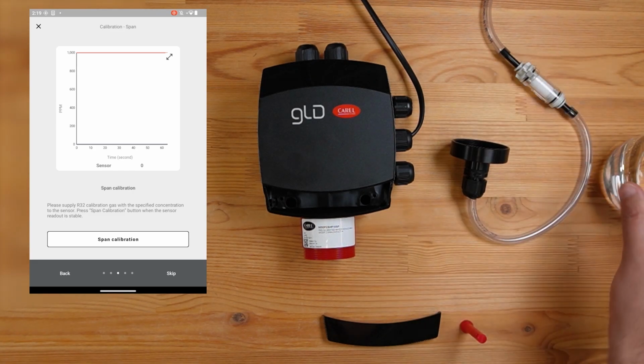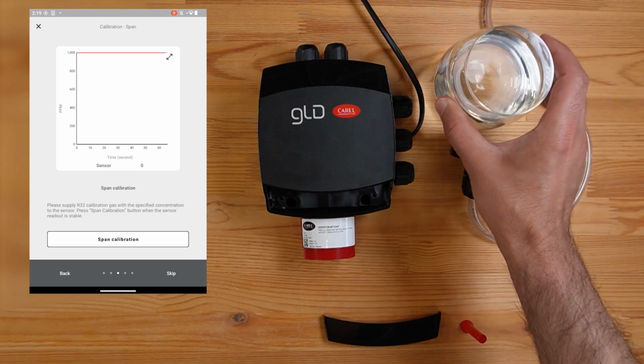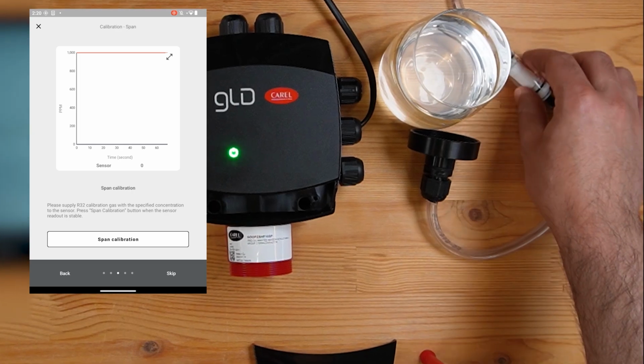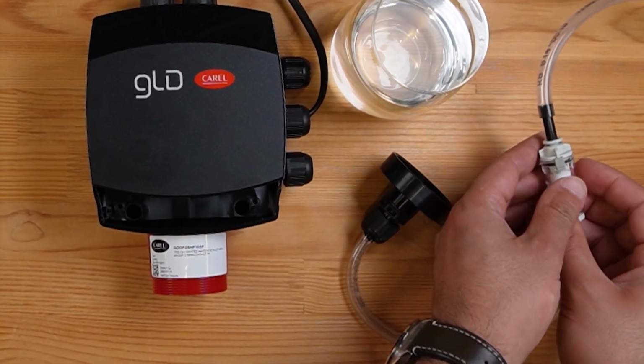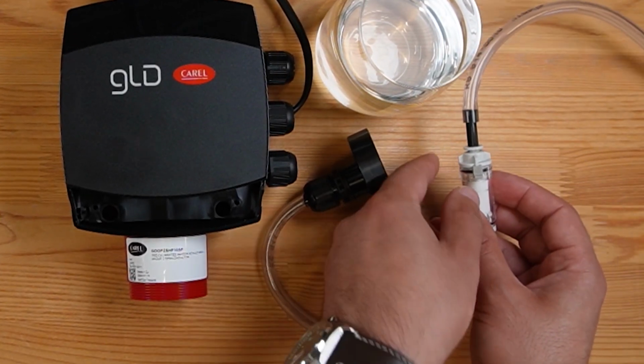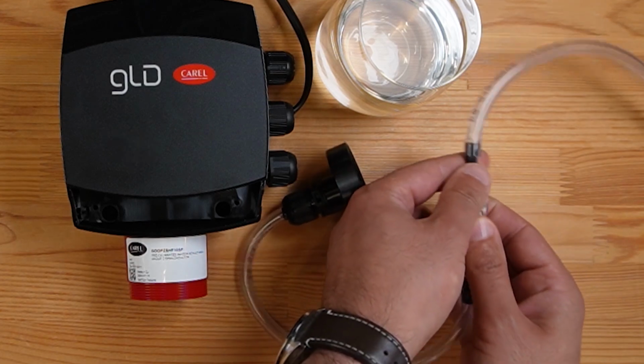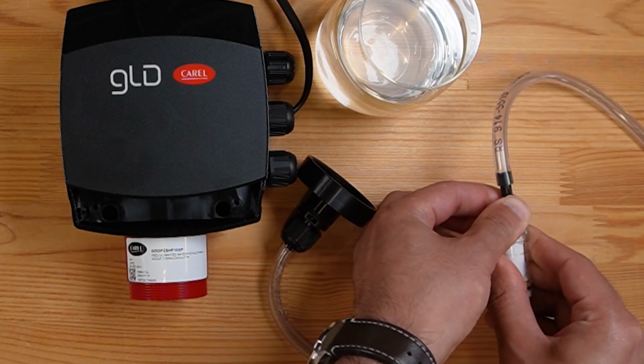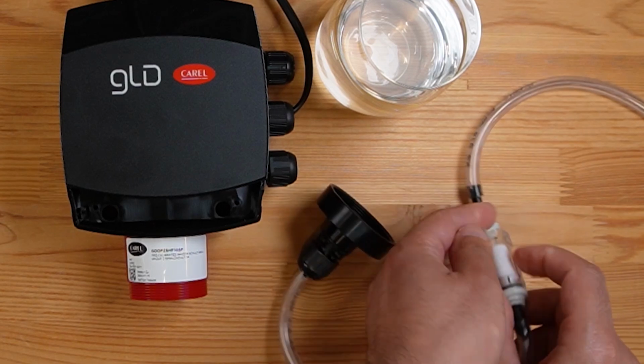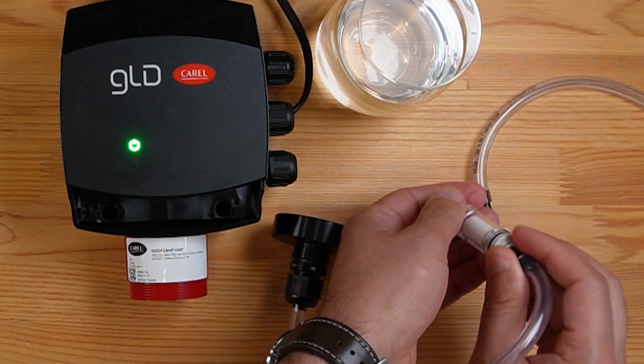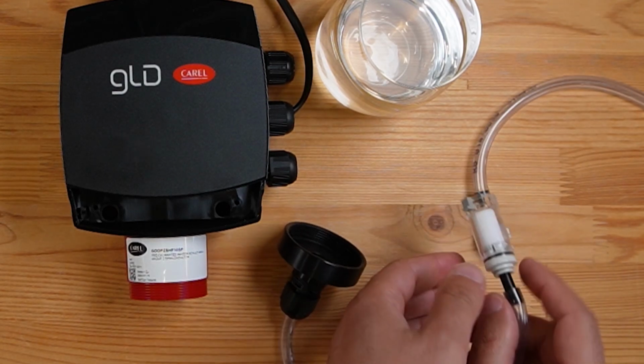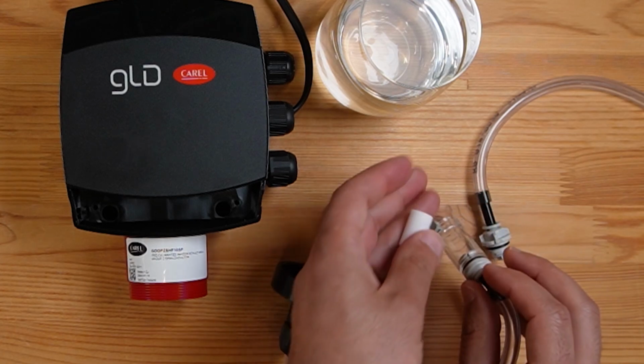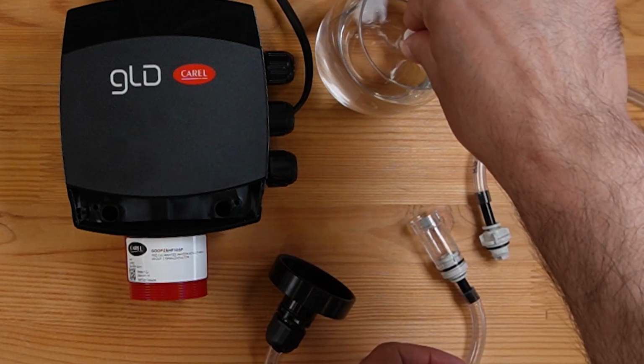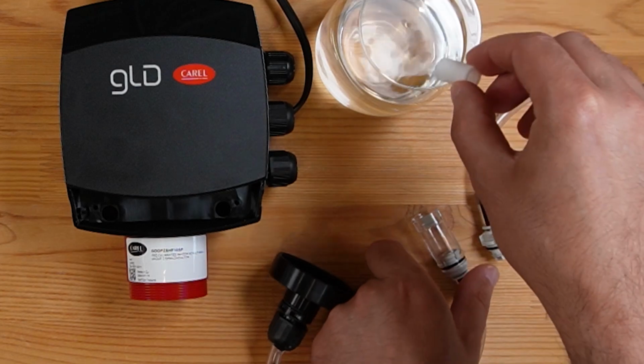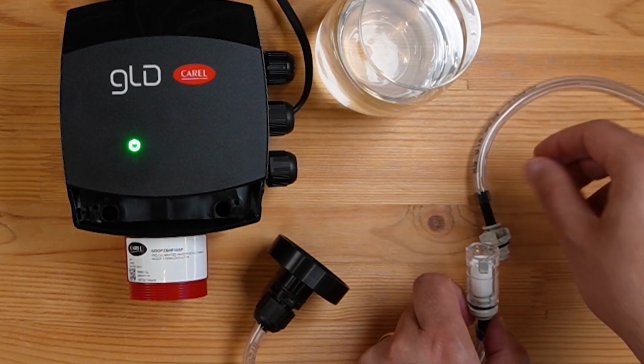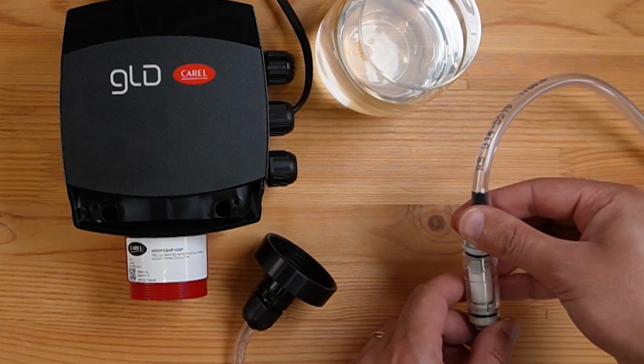Before you mount the calibration kit to the sensor head, it is important that the filter in the cylinder is moist. Remove the cylinder by pressing the lever and then detaching the two parts. Immerse the cylinder in a container filled with tap water for a few seconds. Place it back in the previous position and close the filter.